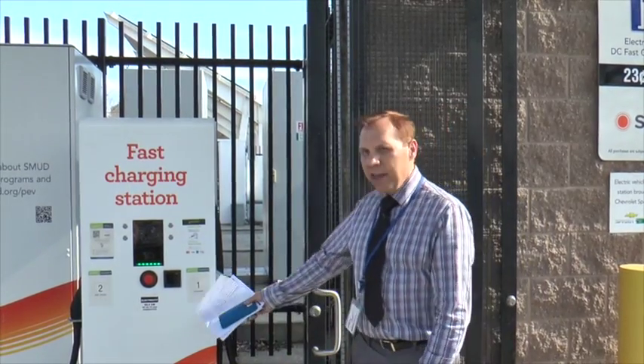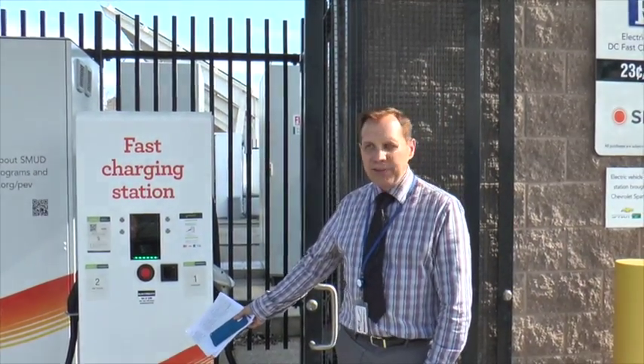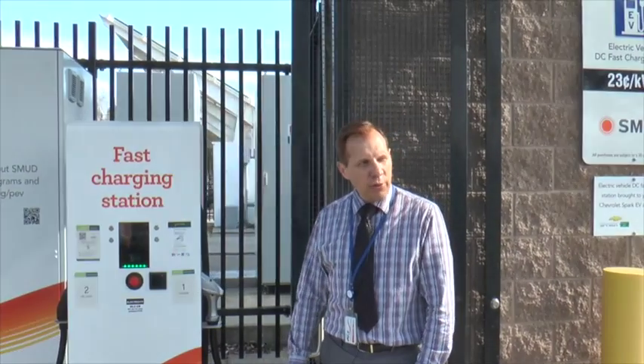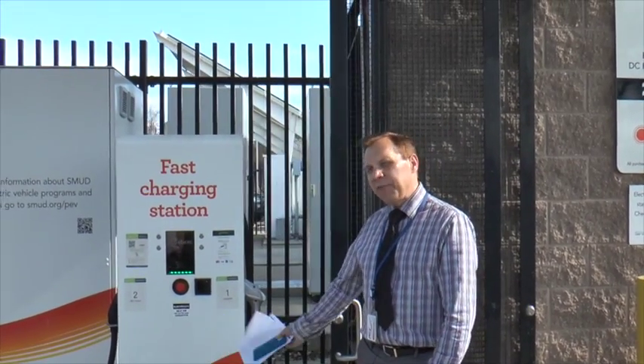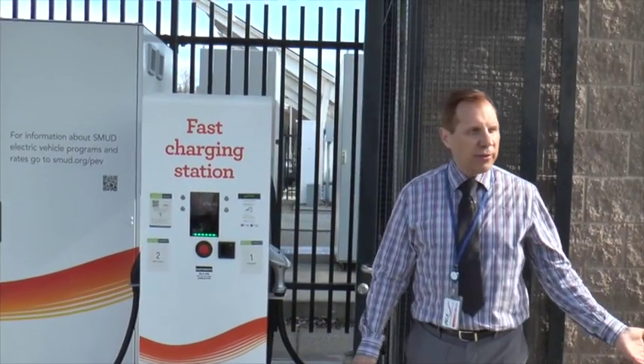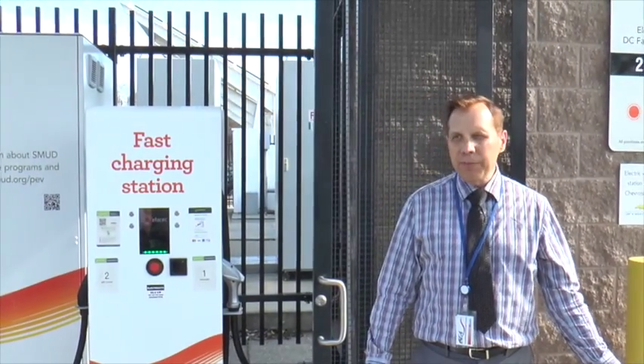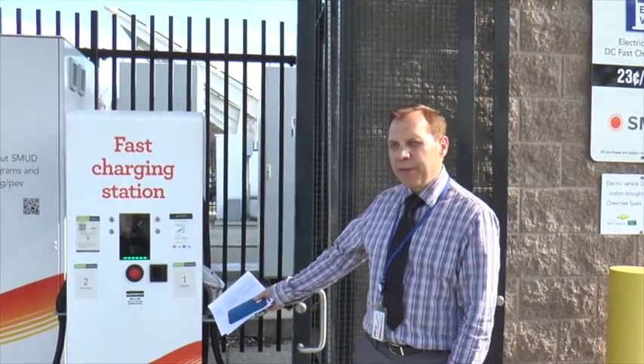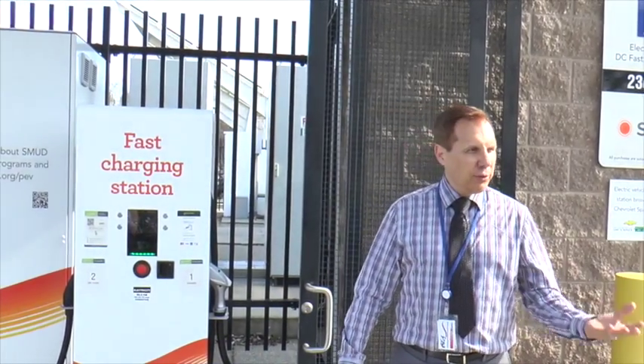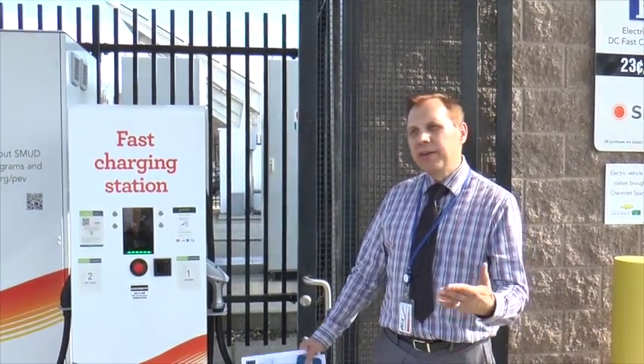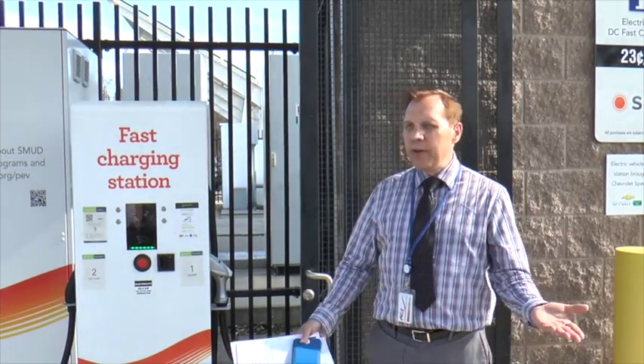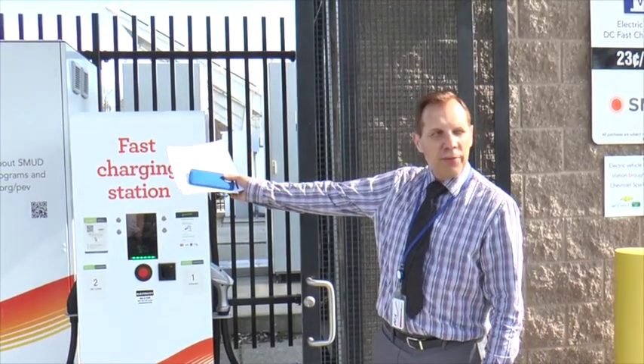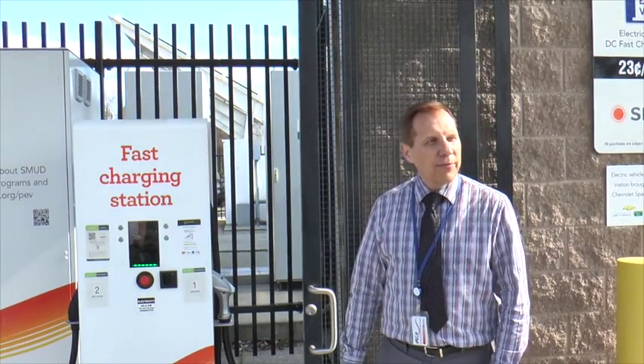They do make a 25 kW DC fast charger that runs on 208, and it's half the price. 208 is standard industrial power. Instead of 480 three-phase at 100 amps, you're now at 208 three-phase at 100 amps, so your costs go down, and you're into that smaller switchgear we saw over there, not the big commercial stuff.